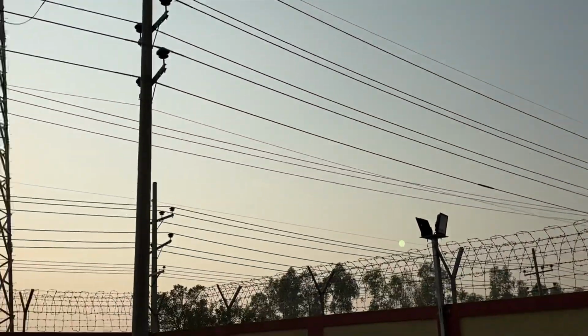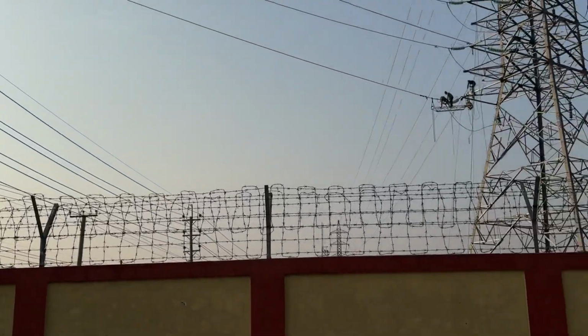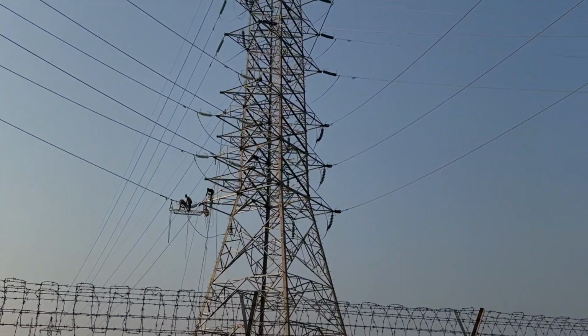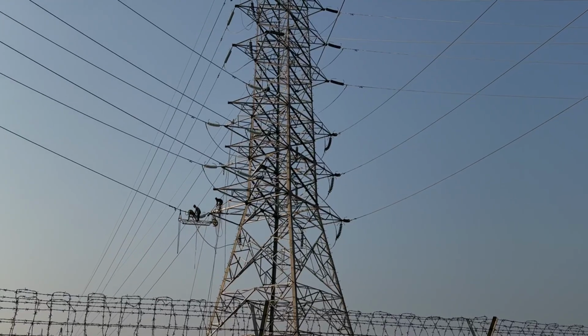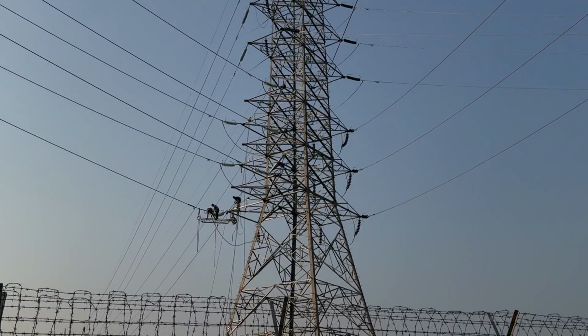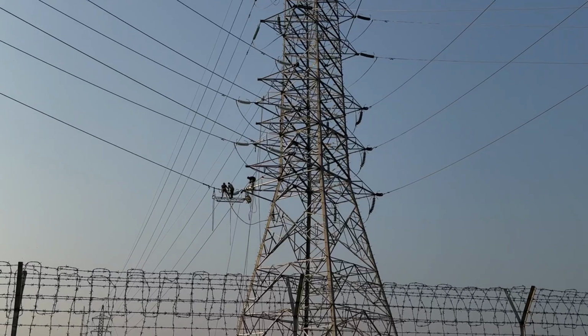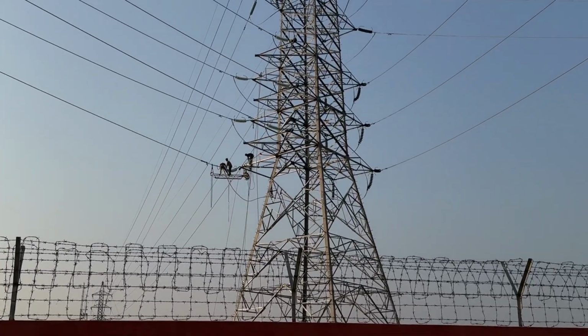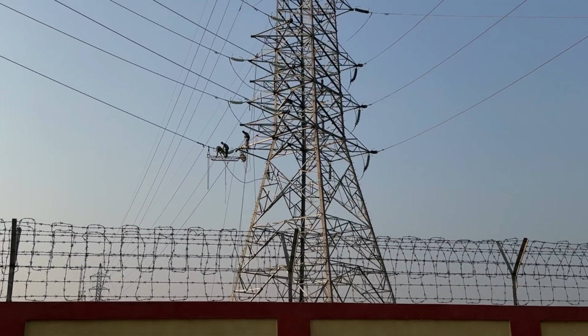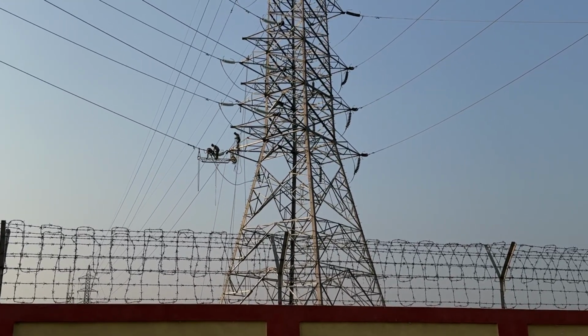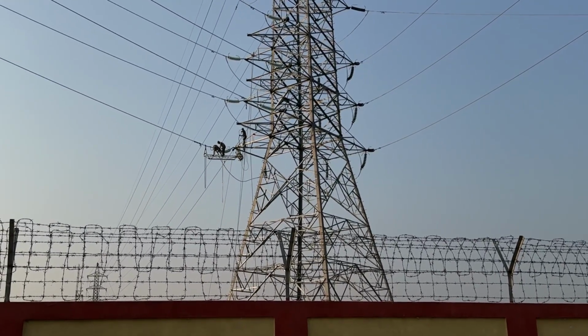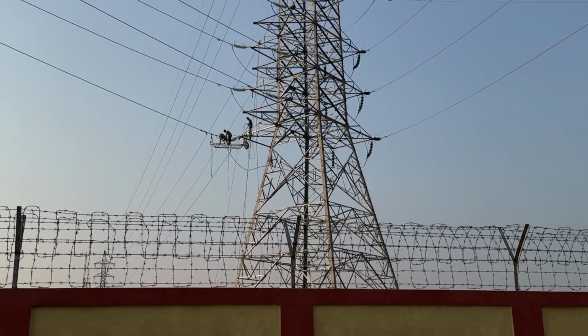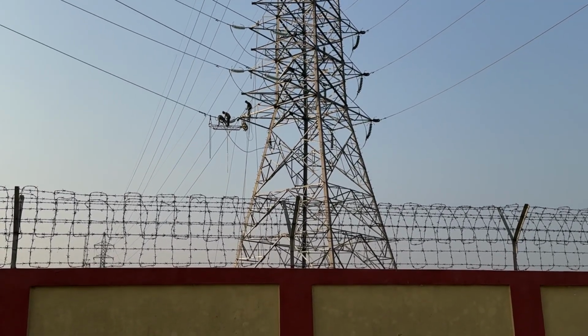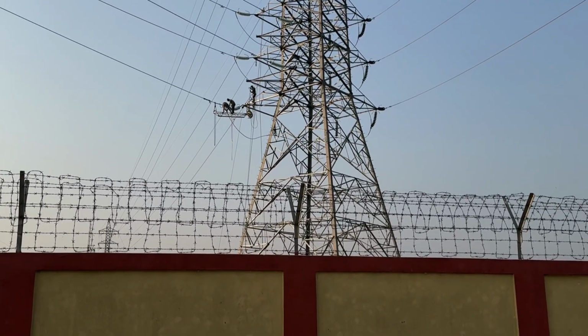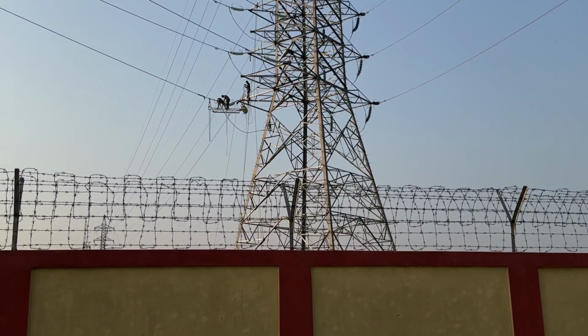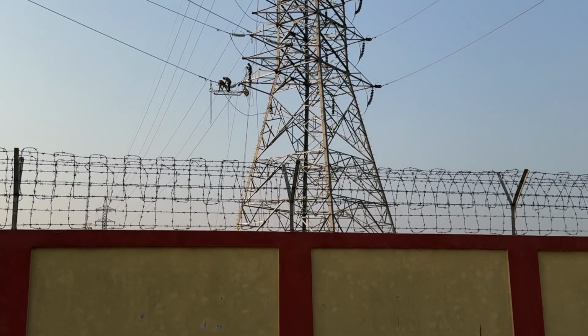There was an existing transmission line, but LILO work is continuing here. What is LILO? Just assume there is an existing transmission line of 3-phase conductors. If we cut the 3 conductors, there will be 6 terminals. These 6 terminals are coming into this substation.